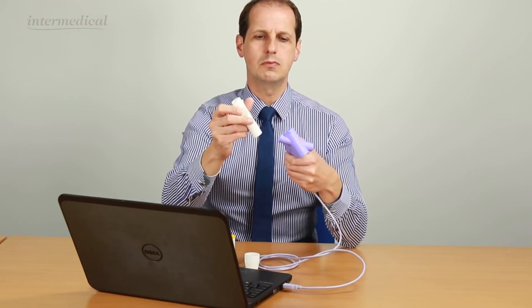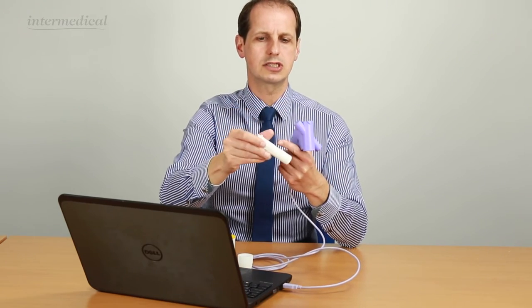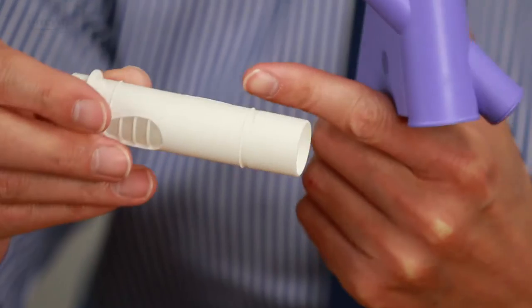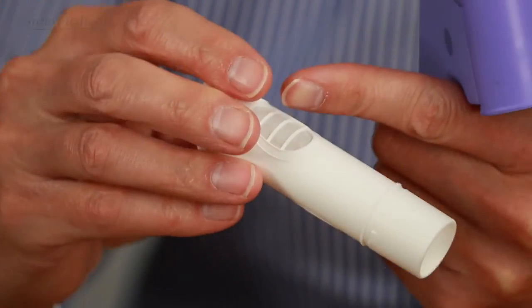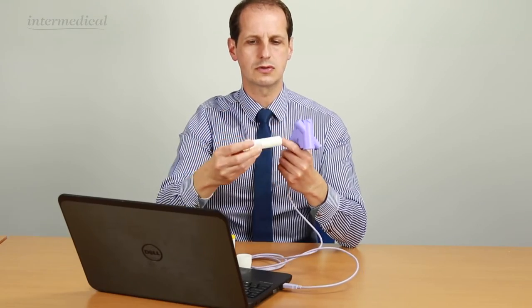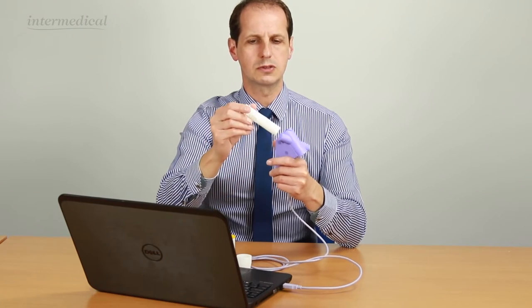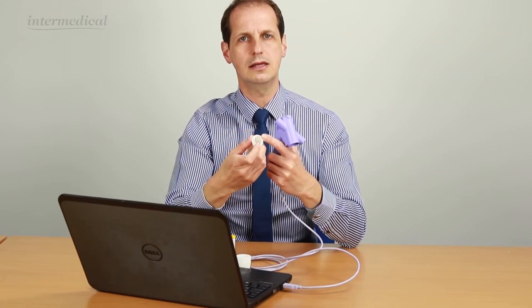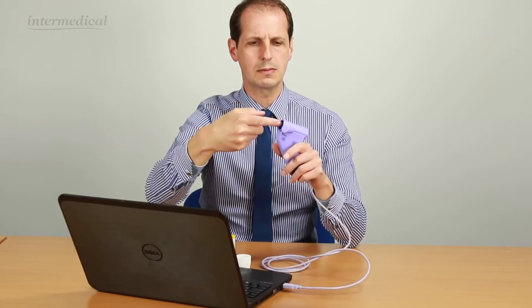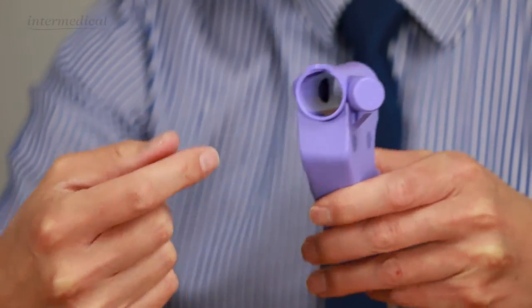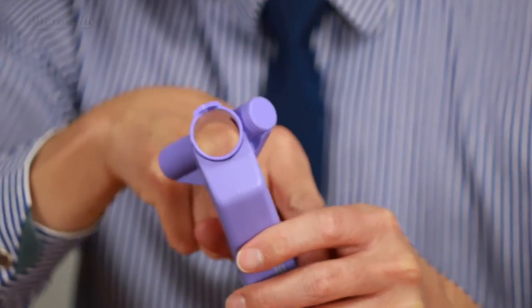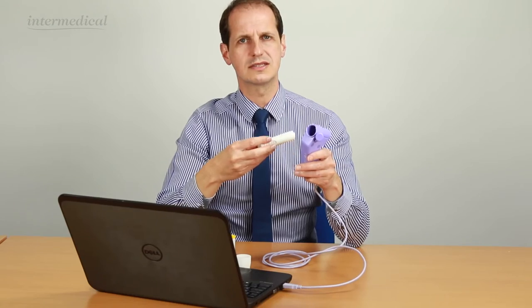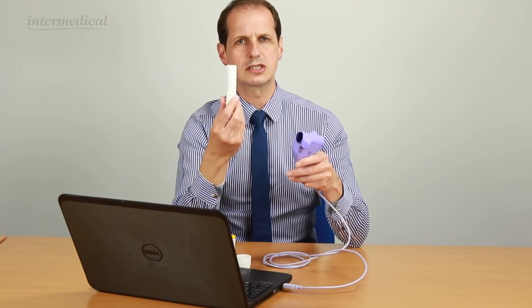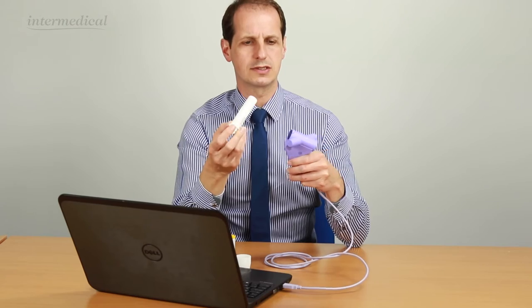The spirette M would go into here. Now on each side of the spirette M is a window. Now in that window is a filter. So where the sound passes through, there's a filter, which means anything that's inside here, i.e. the patient's breath, will not come into contact in here. So for cleaning, you can just wipe the outside of this down with a sterilizing wipe and change the spirette M on a weekly basis.